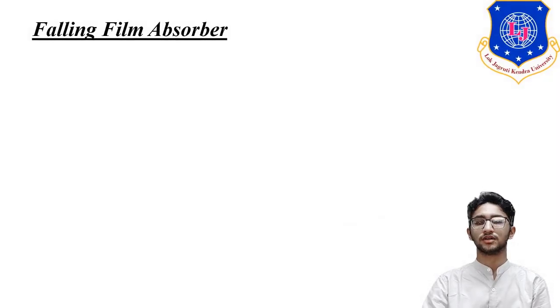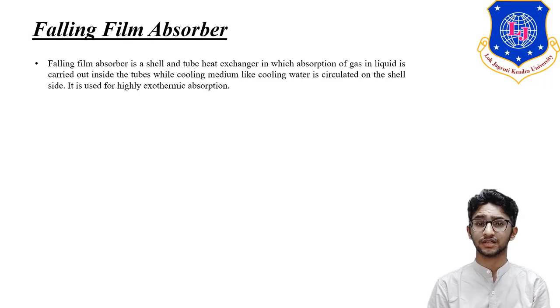Now we will talk about the falling film absorber. So the falling film absorber is generally a shell and tube heat exchanger in which the absorption of a gas in a liquid is carried out inside the tube, while the cooling medium like cooling water will be circulated over the shell side. They are generally used for a very high exothermic absorption.